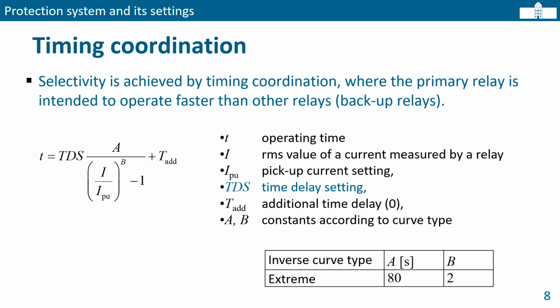Selectivity is achieved by timing coordination. The main idea is that the primary relay is intended to operate faster than the backup relay. Operation time of the relay is described by the equation given here, and the unknown parameter is the time delay setting TDS. Other parameters A and B depend on the inverse curve type. In the case of extremely inverse, these values are 80 and 2. The additional time delay is set to 0, and the current is marked with the symbol I, while the pickup current setting is marked with the symbol IPU.